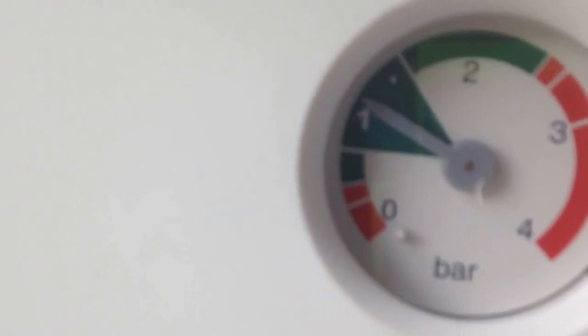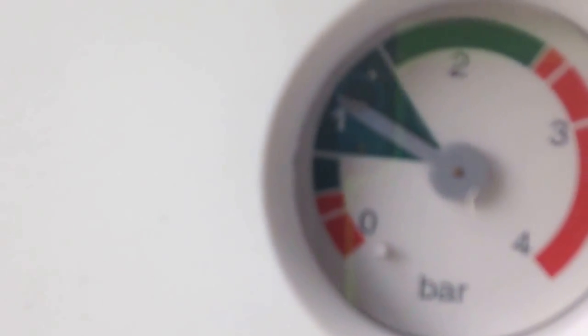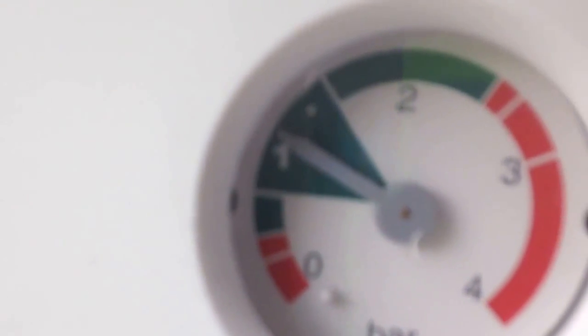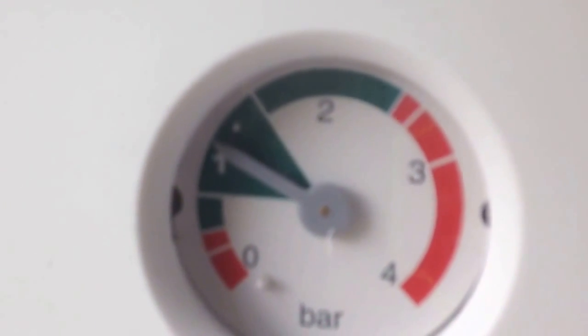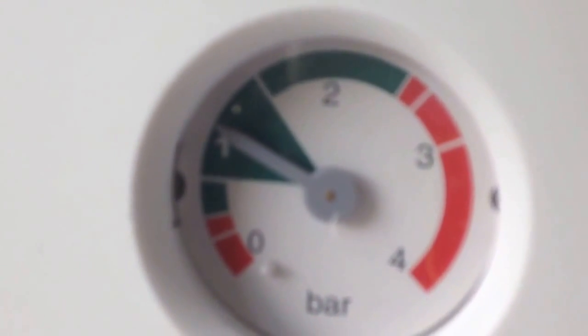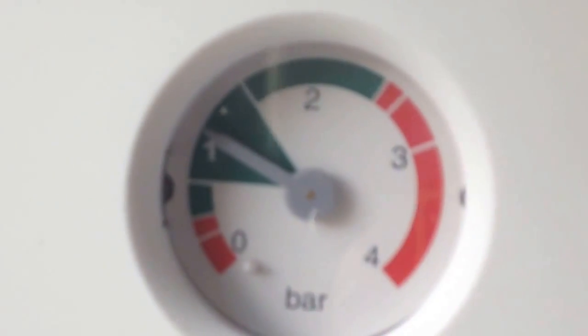Obviously it's showing you in green, so anything there is okay. When it drops into the red at the bottom, the boiler should stop working. And if you put too much water in at the top, you could blow the safety valve, so that's dangerous as well. You have to let some of the pressure off.